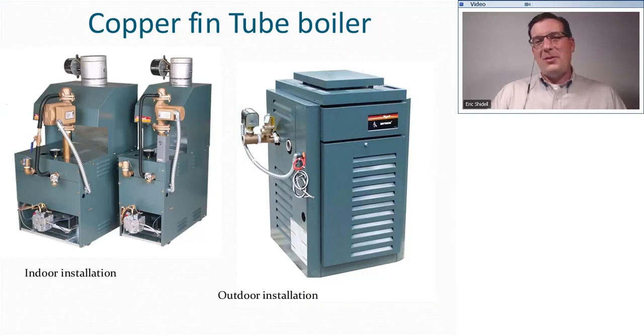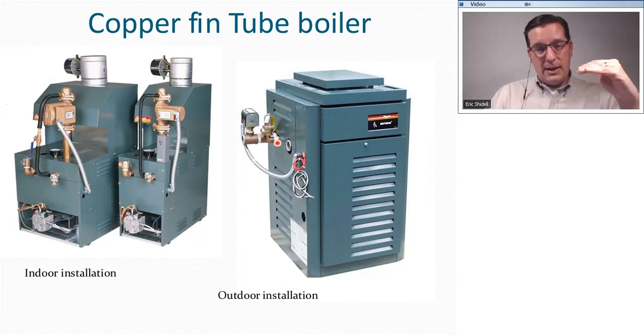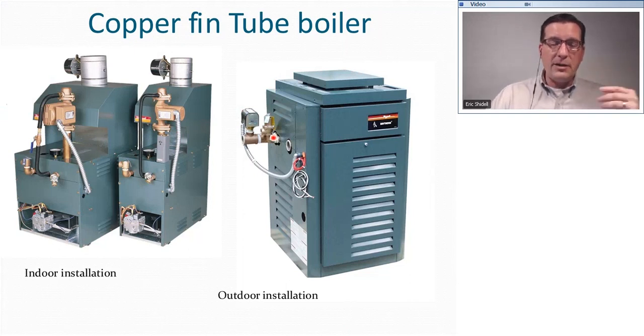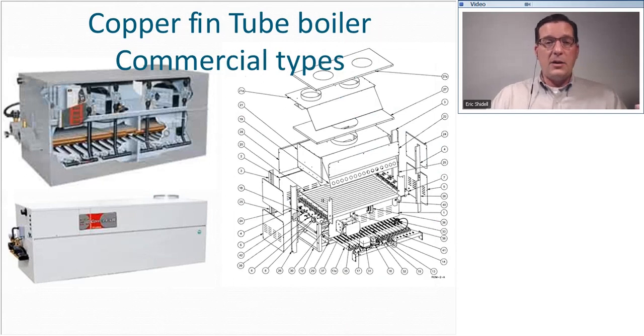Copper fin tube boilers don't have that same thing going on. One of the defining features of a copper fin tube boiler is that the water enters and leaves at the same physical level. For example, on these we have water entering and leaving both on the top side. On this one, we have water entering and leaving both on the side at the same level, entering, leaving, or this could be entering and leaving. It's a little harder to tell which one's the entering and which one's the leaving on a copper fin tube boiler. This is a commercial copper fin tube boiler.